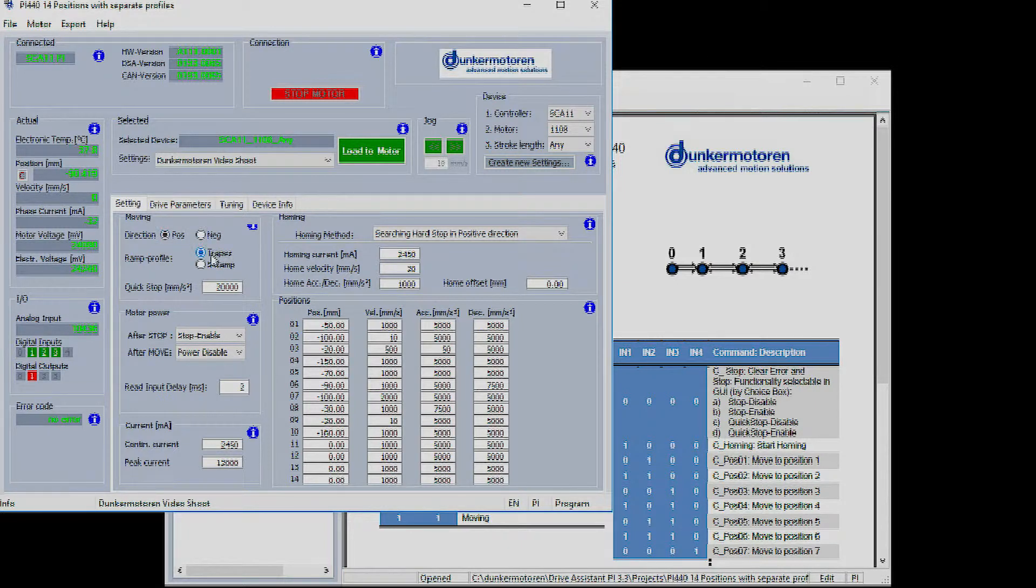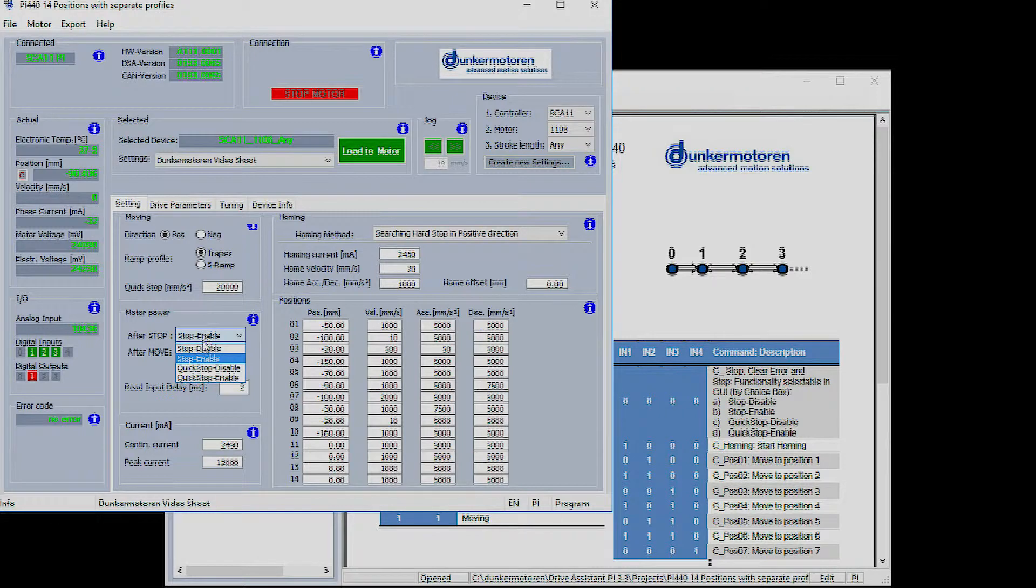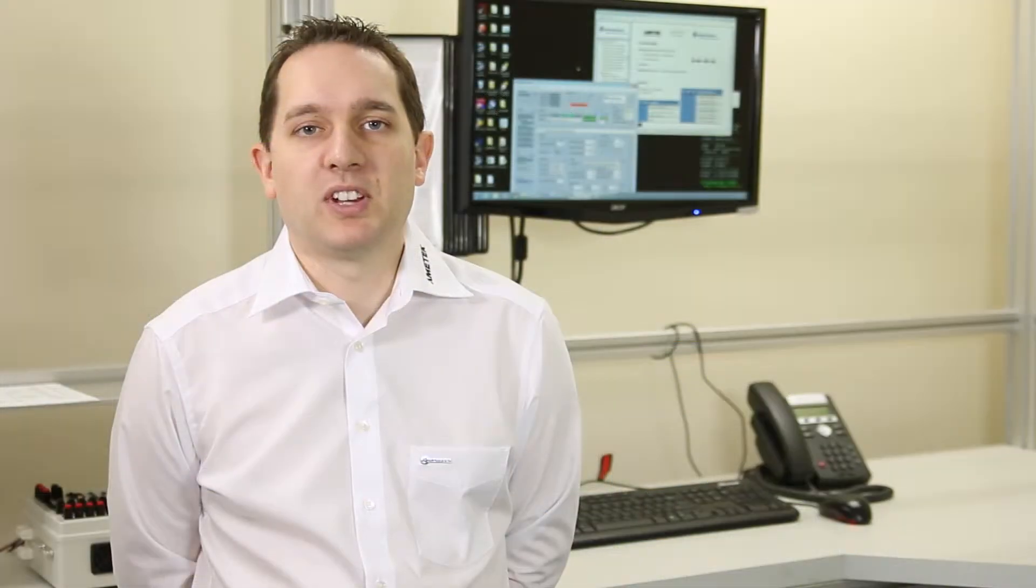The homing method can be selected: reference switch, limit switch or hard stop. Within this the velocity of the home can be set along with a homing current and any offset for the home position.